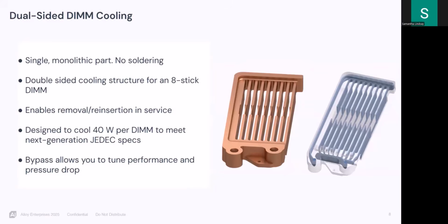With conduction, eventually the thermal resistance gets high enough that you just can't pull enough heat out of the sticks. The crushed copper tubes also have challenges getting down to really fine DIMM pitches, and they're not very pressure resistant, because you've already yielded the tube to squish it into the form factor you want.